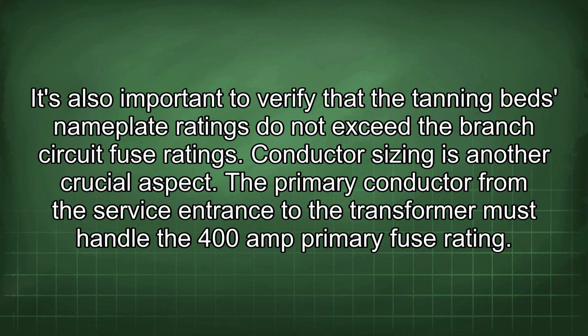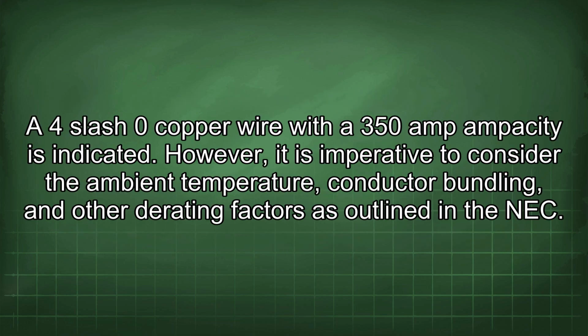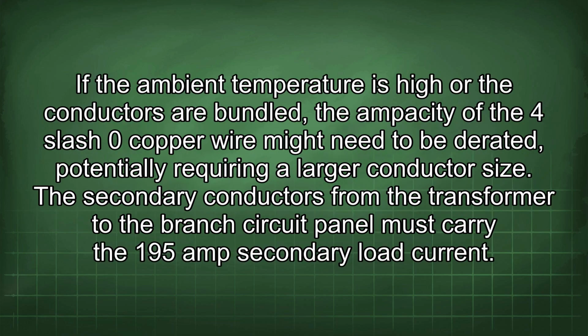Conductor sizing is another crucial aspect. The primary conductor from the service entrance to the transformer must handle the 400 amp primary fuse rating. A 4/0 copper wire with a 350 amp ampacity is indicated. However, it is imperative to consider the ambient temperature, conductor bundling, and other derating factors as outlined in the NEC. If the ambient temperature is high or the conductors are bundled, the ampacity of the 4/0 copper wire might need to be derated, potentially requiring a larger conductor size.